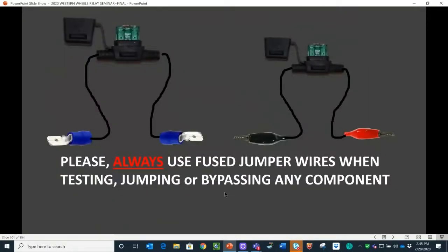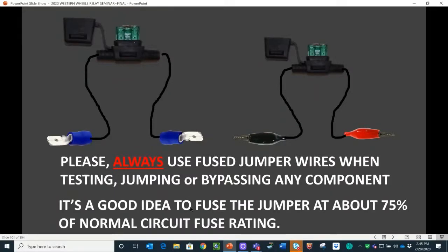Again, always use fused jumper wires. And here is where I said, you want to fuse the jumper at about 75% of the normal circuit fuse rating. I knew I said that somewhere in there.